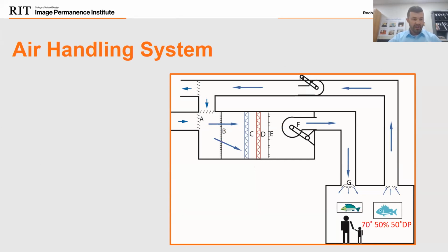I want to turn our pen on and hope for the best, because sometimes our pen gives us some issues, but this is the condition we're hoping for. This is my gallery. Forgive me for not having a great artist representation. It's clip art, and I get a lot of grief for having used it. So this is our gallery for our space. And the conditions we're aiming for are 70 degrees, 50% relative humidity, and a 50-degree dew point.